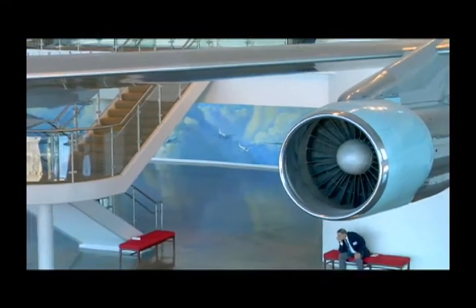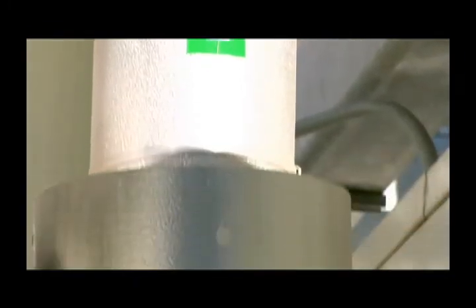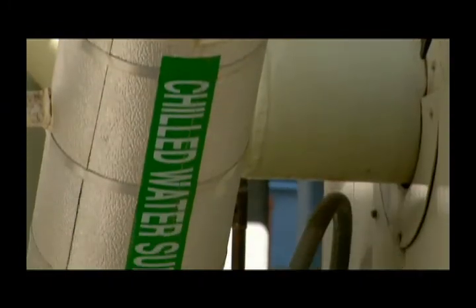It's turning at 96,000 RPM, one moving part, air bearings, no oil, no antifreeze. So highly reliable, very simple design, but with the recuperator we see much higher efficiencies than other products in the market today. The turbines use natural gas, which is a very clean fuel. They burn natural gas, which runs the turbines, which gives us up to 960 kilowatts of electricity. That exhaust gas from the turbines running is collected and goes into an absorption chiller. That chiller has a closed water loop through it, which chills, and that gives us our cold water for our air conditioning system.